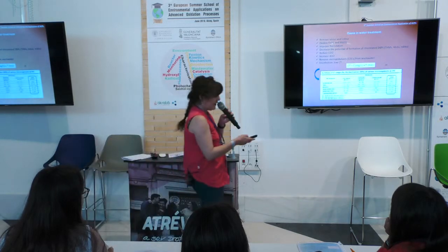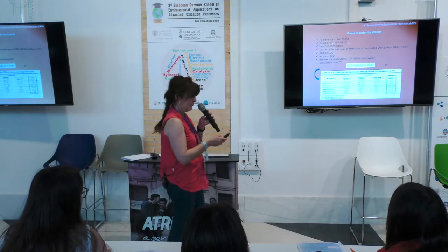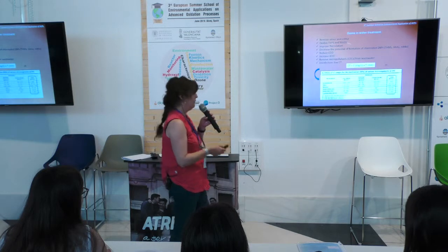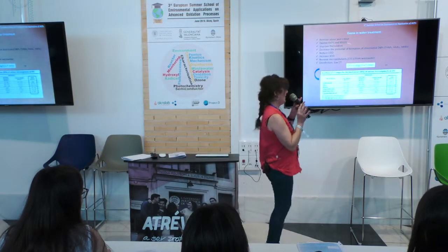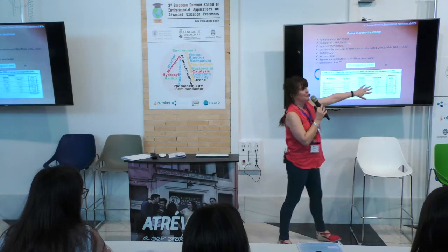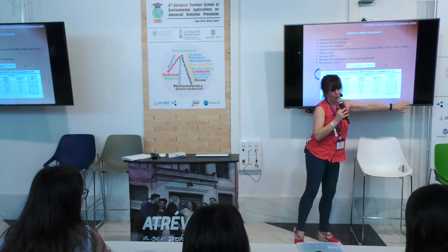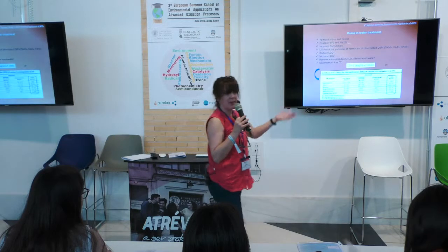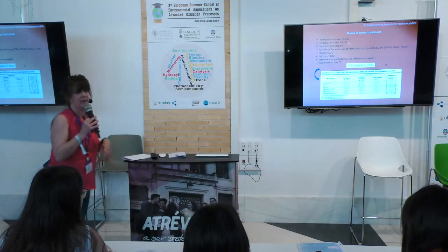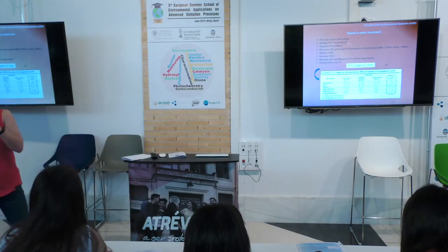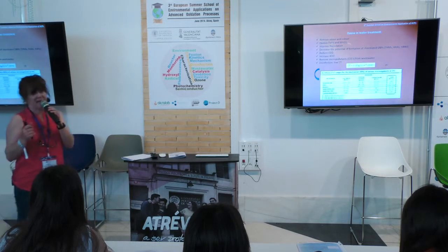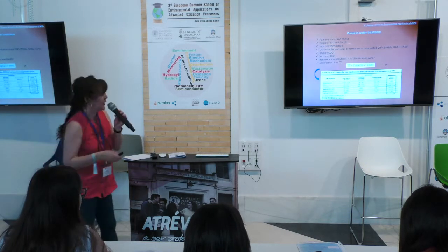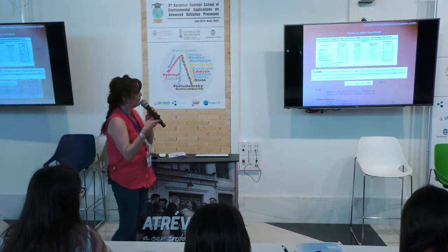If we compare the values corresponding to ozone, the CT values or ranges are much lower than for the rest of the disinfectants. It means that the lower the CT, the higher the disinfectant capacity is. So let's see an example.